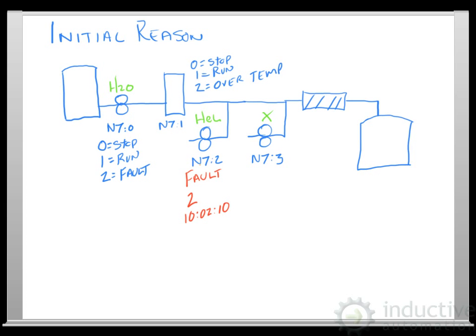And then when that shuts off, we can't have our product without our HCl in it. So we have to stop the process, and then the PLC program would stop the water right away. The temperature would start scaling back. This ingredient would have to stop because otherwise we just fill up the pipe with this ingredient and wouldn't have the water and the HCl. So everything stops immediately. There's no accumulation between any of these.